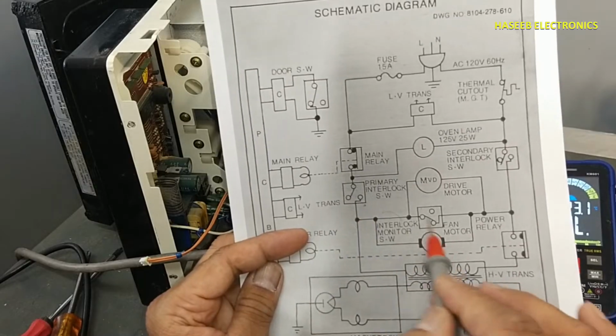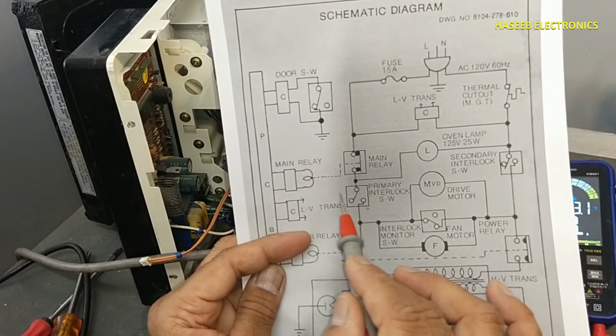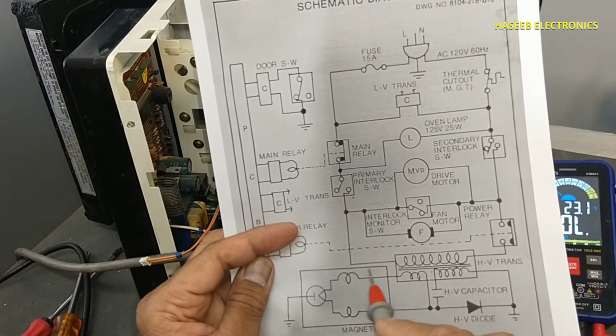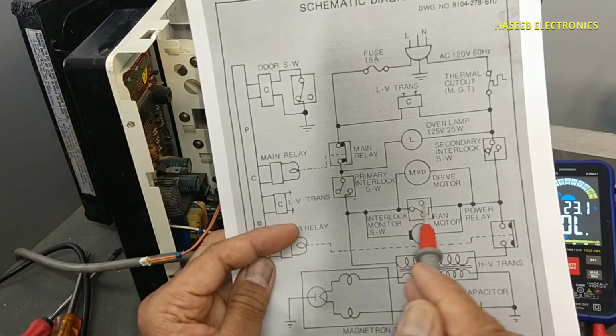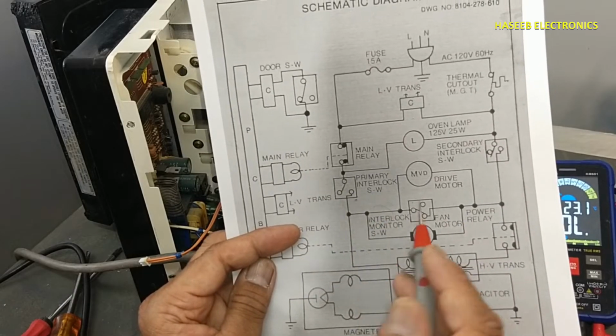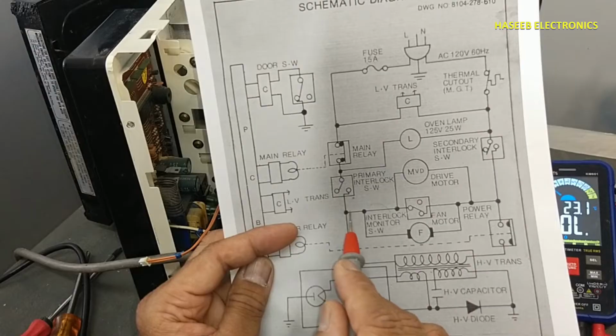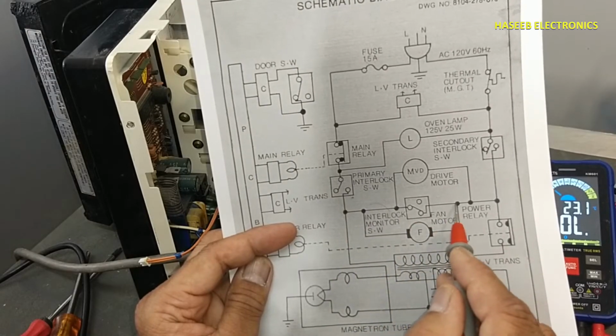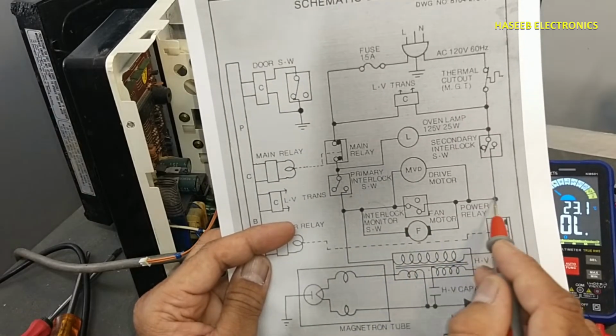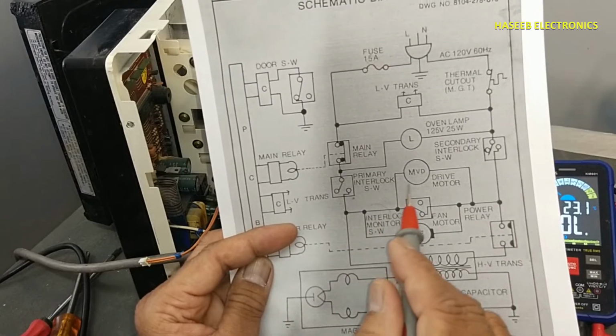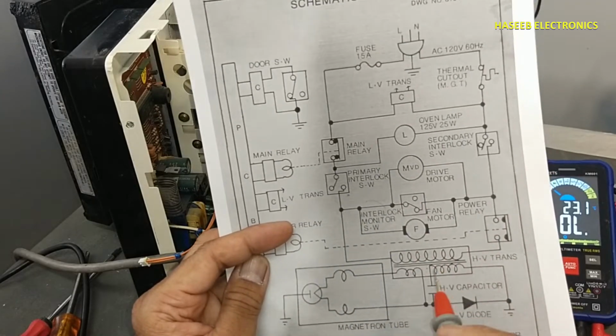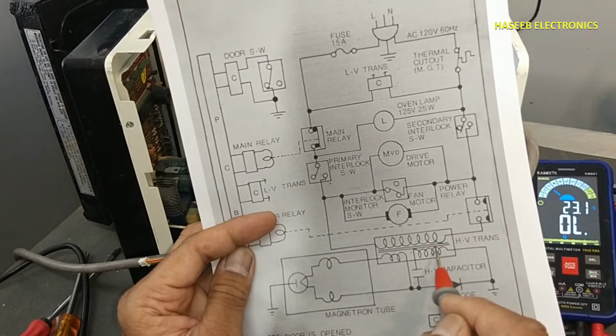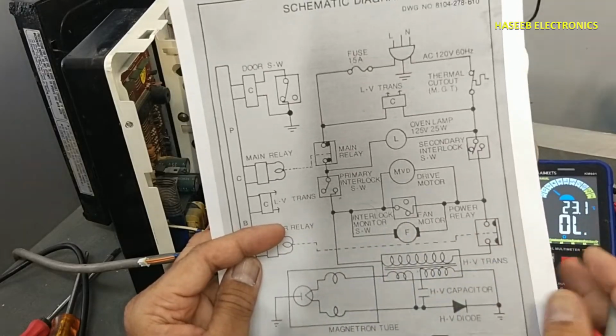When the door is opened, this switch will open so that the supply will not pass to this side. But at that time, for additional safety, there is another interlock monitor. It will allow a short circuit between the motor, fan and this transformer. So it is an extra layer of safety here.